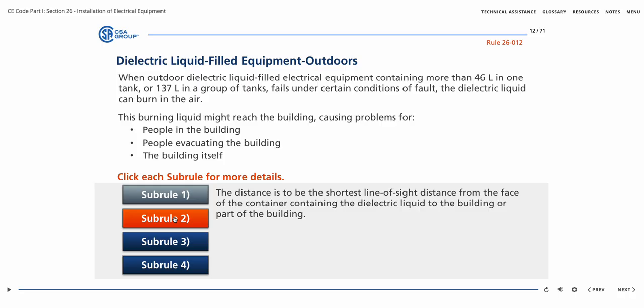Sub-Rule 2 gives the requirements for how the 6 meters distance in Sub-Rule 1 is to be measured. The distance is to be the shortest line of sight distance from the face of the container containing the dielectric liquid to the building or part of the building.